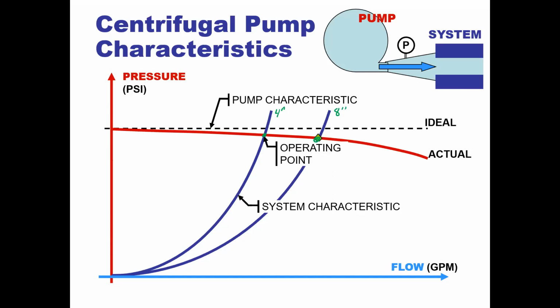A lot more gallons per minute, but we lose just a slight bit of pressure. We're going to be going from about here to about like here, right? So it's not that much of a fall off, maybe 1 or 2 PSI, but we'll gain probably like 20 gallons per minute. And when we make this thing wide open, pretty much no restriction, our system characteristic is going to go way over to the right, again following it to this spot. Let's call that a 12-inch piece of pipe, no restriction. And as you can see, we are going to have a higher and higher fall off. So from where we were originally on that 4-inch, we went all the way down to our 12-inch pipe, so maybe we do have like a 5 PSI, 10 PSI difference, but we're going to gain maybe 80 gallons per minute of flow.